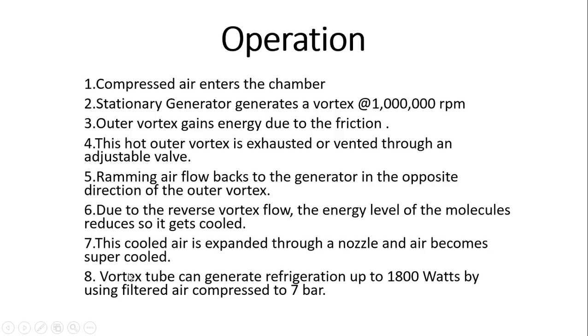Now, a vortex tube can generate refrigeration effect up to 1.8 kW by using air which is compressed to 7 bar.